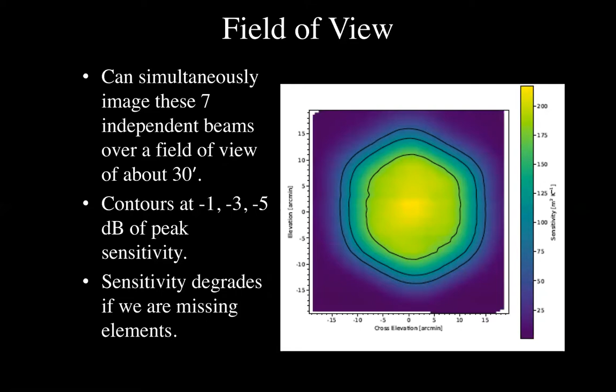When we form beams, we typically use a process called max signal to noise ratio. That's to get the maximum sensitivity at the peak of the beam. It doesn't provide any constraints on the beam shape. As I said, we can form 7 Nyquist sampled beams in the field of view.